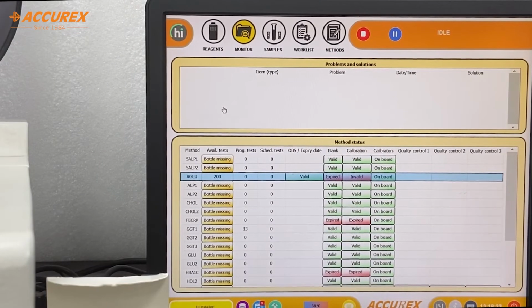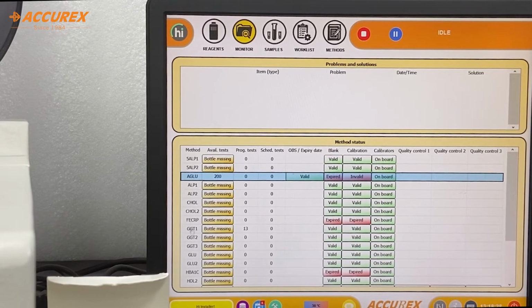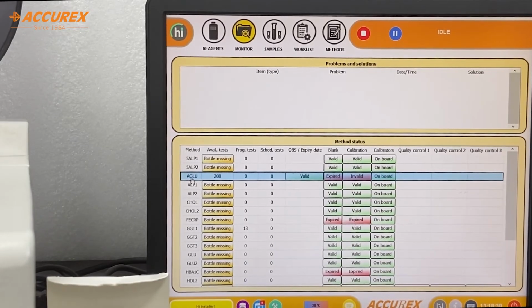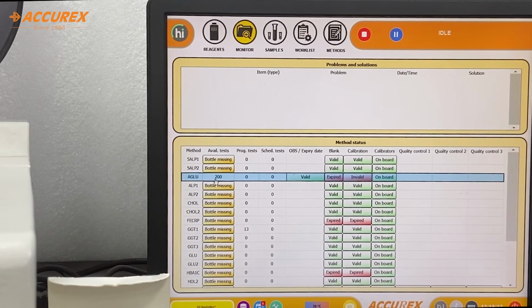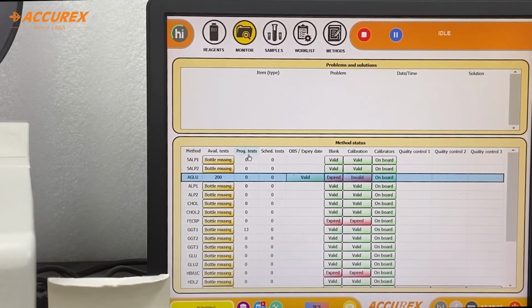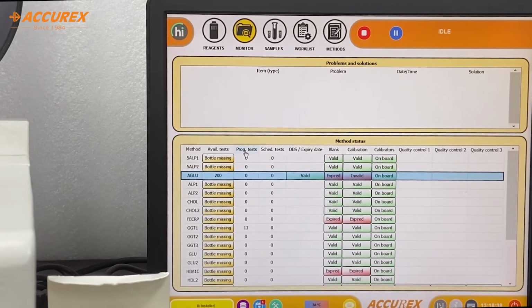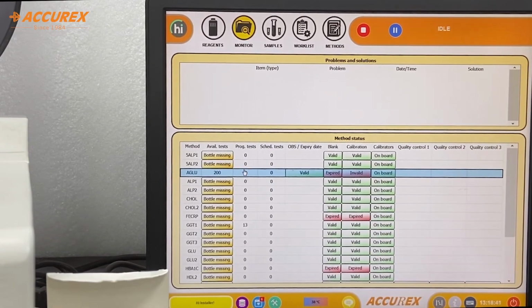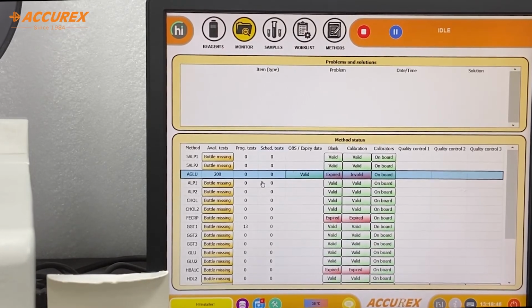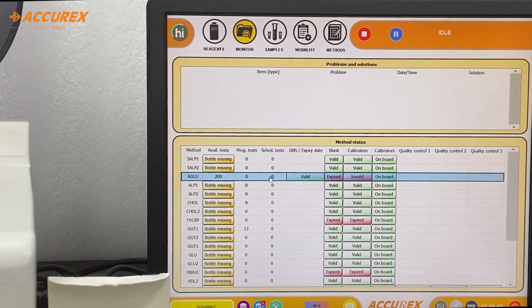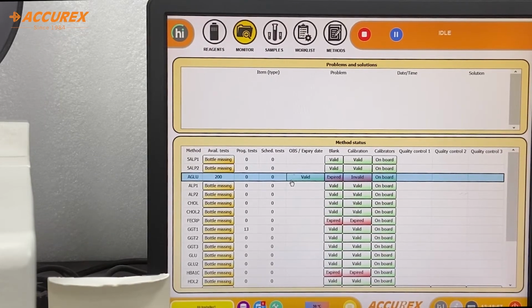So the next step will be the monitor. You can see in the monitor screen the number of tests and the number of methods which we have scanned and kept on board. Currently, we have scanned the bottle of glucose, and it is showing 200 tests available. Next to that, there is a program test. This parameter shows how many programs you have fed and how many tests have been programmed on board. Next to that, there is a scheduled test. It shows the number of tests running, the current status. Next to that, there is the OBS and expire date. It will show the current status of the reagent, whether it is valid or invalid. OBS basically shows the onboard stability of the reagent.